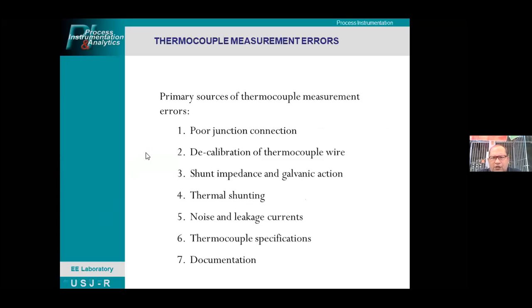So these are the primary sources of thermocouple measurement errors. Poor junction connections, the junction between two metals, the point that is welded or soldered. But now, if you are purchasing these thermocouples, they are already well welded or well soldered. But if you make it yourself, it will be possible to have errors in reading thermocouple measurements. Then the decalibration of thermocouple wire is also possible. Shunt impedance and galvanic action, thermal shunting, noise and leakage currents, thermocouple specification, and some documentation. So these are the common sources of thermocouple errors or measurement errors.